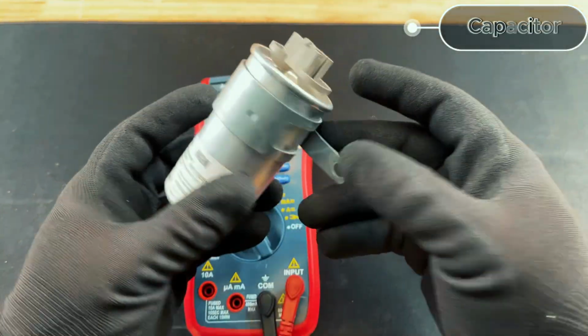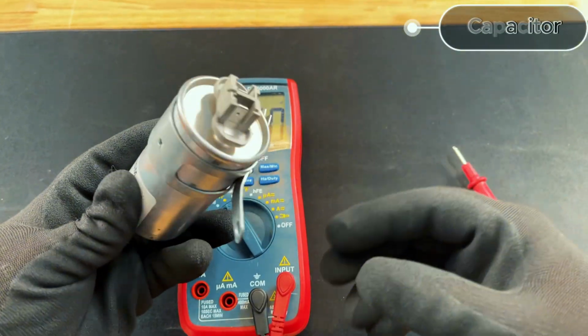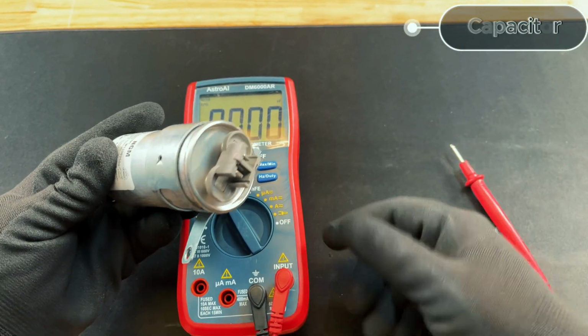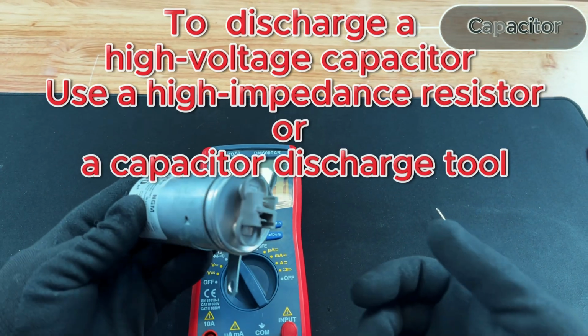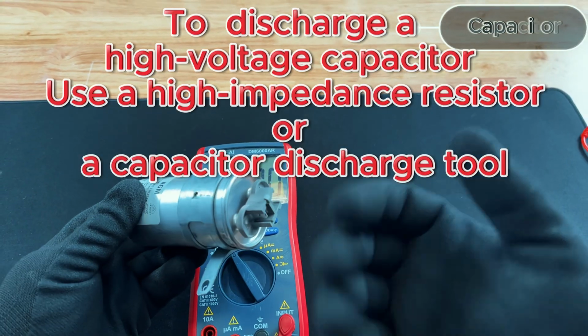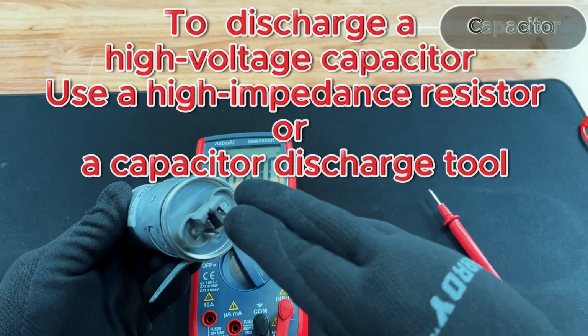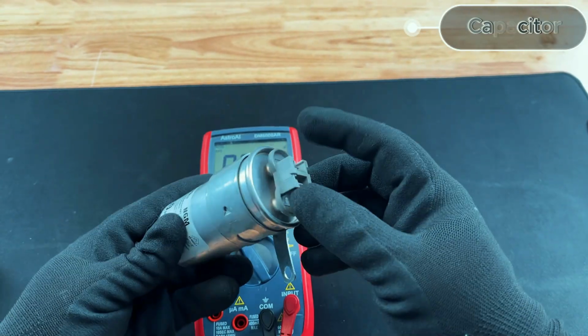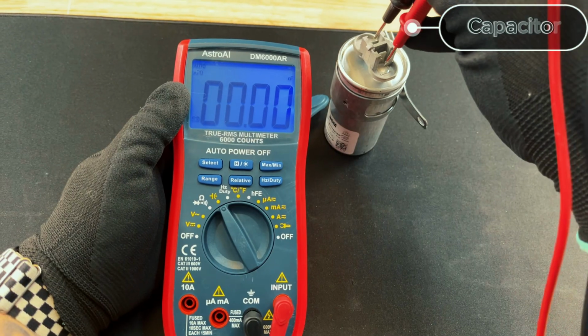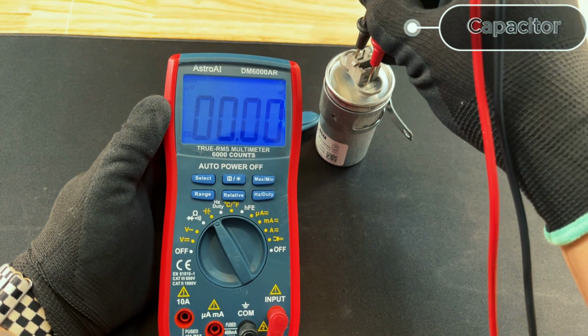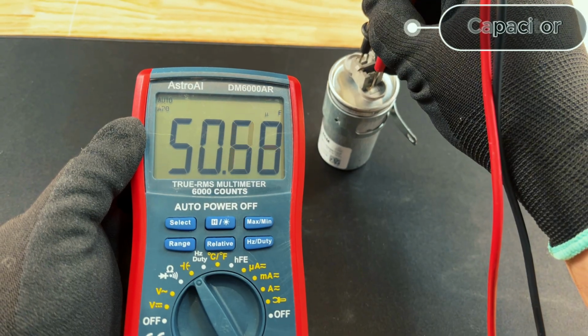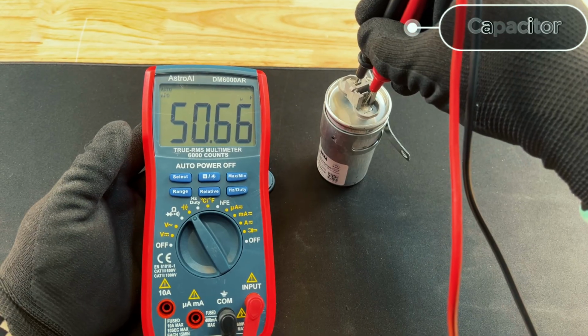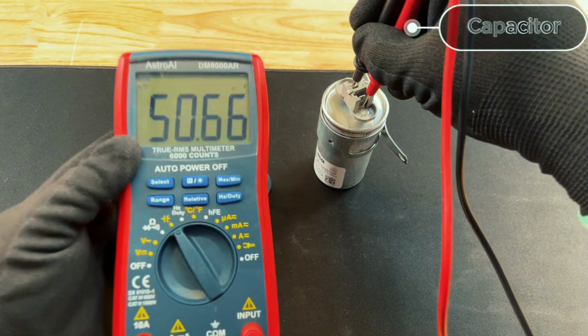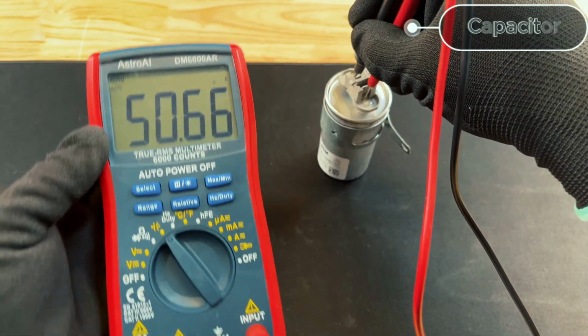Discharge your capacitors when you're testing them or before you touch them. And what you can do is short them out. That's either using insulated needle nose pliers or insulated screwdrivers, and you just want to touch both of those. Now this has already been discharged, so you're good there. All we're going to do is just touch both of those prongs there. There we go. And some meters do have a delay. As you can see, we're reading 50 microfarad, so that's reading correct.